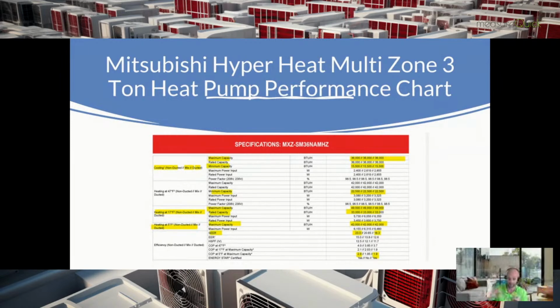And then when you get into matching these up, you have to look at the engineering data, because when you get one to many like this, you end up losing capacity on some of these things. So if you've got a 9,000 BTU and a 12,000 BTU coming off this somewhere, and they all call at the same time, you're not getting 9,000, 9,000, 12,000 out of them. You're going to get something less than that. You're going to get around 8,500 BTUs or around 11,500 or 11,000 BTUs out of those indoor heads. So you have to pay attention to that too. You're not always getting the same capacity as what's rated as the maximum on this outdoor piece of equipment.